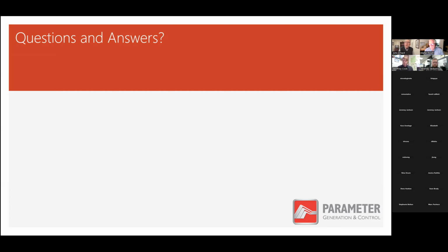In this case, he talked about dehumidifier packets, and I'm thinking that's like a desiccant that we put in with a product to keep moisture out. And I think why it could pull some humidity out is probably very variable in its impact. So to say that you control it with something as variable as a dehumidifier packet could bring some regulatory questions.